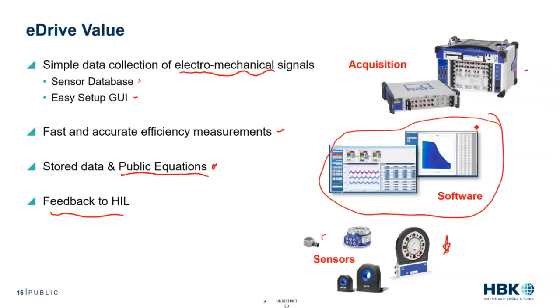One of my points is about accurate measurements and consistent equations. On my screen here is a screenshot of our calibration sheet—our electrical power calibration. We calibrate across a variety of frequencies and across all the ranges of our amplifier, giving us an incredibly accurate measurement, with accuracies around 0.02% of power range. We do this for both the simulated version and the real, test-article version.